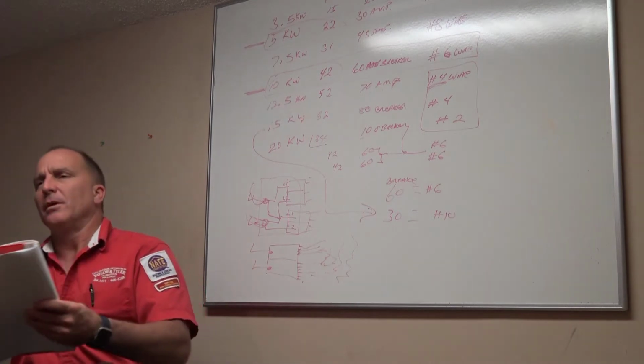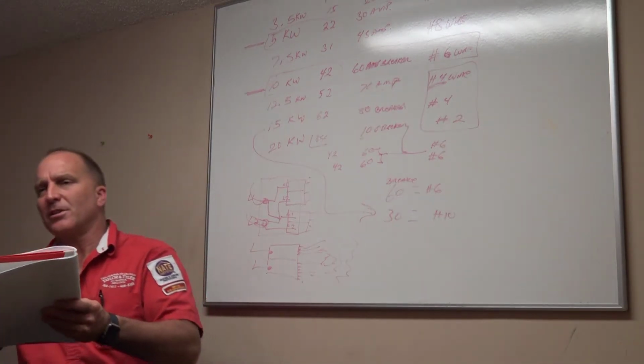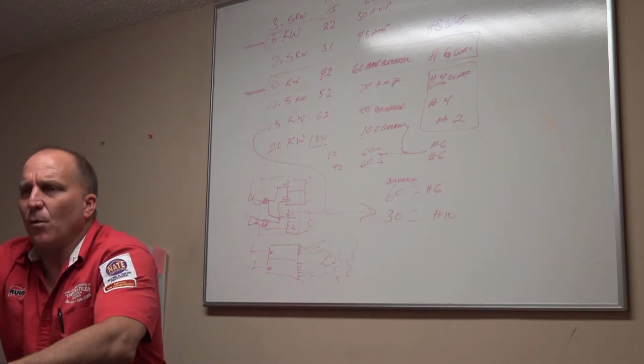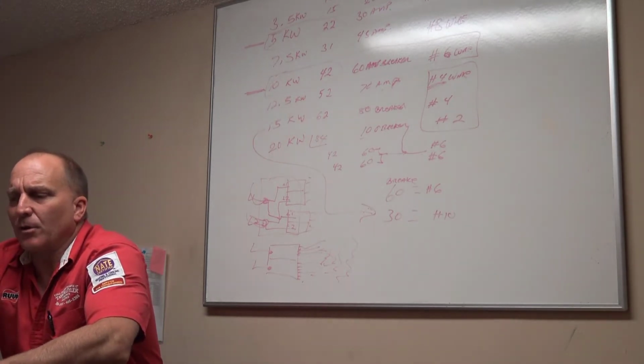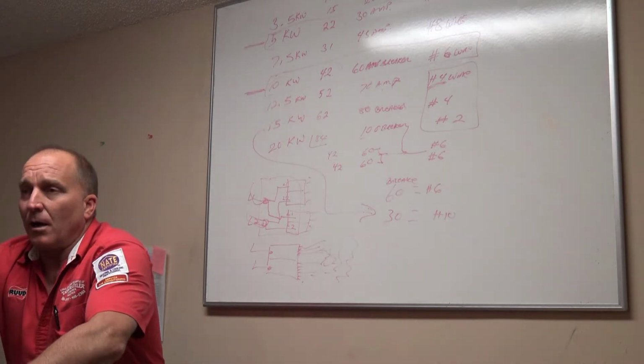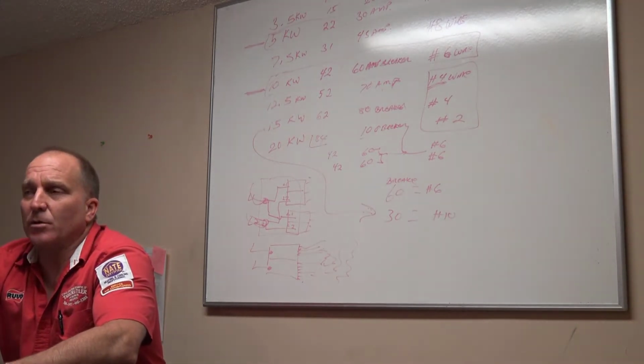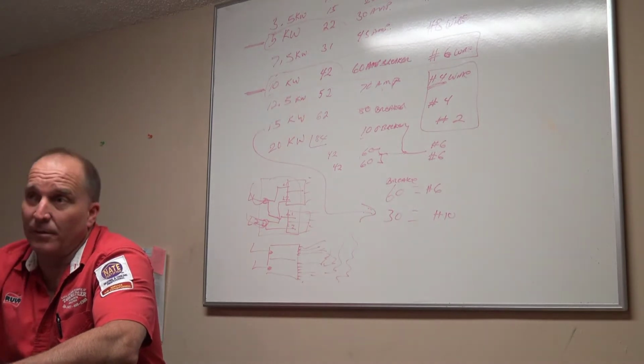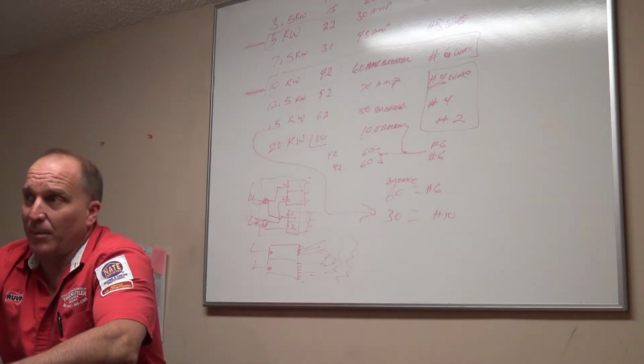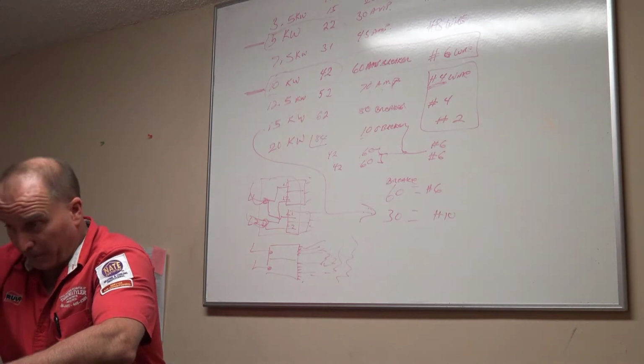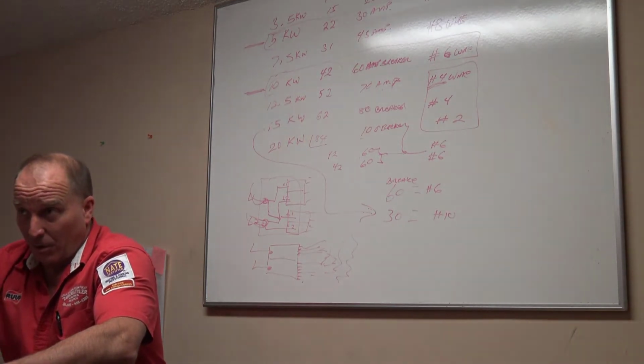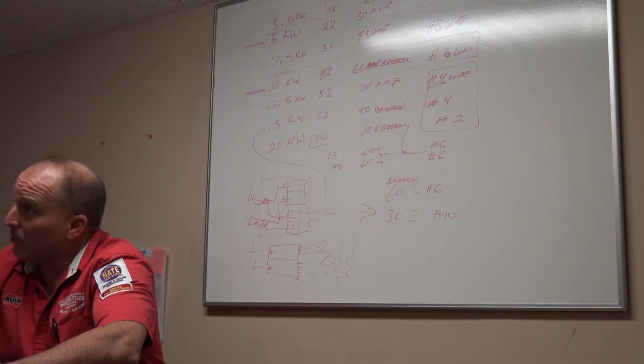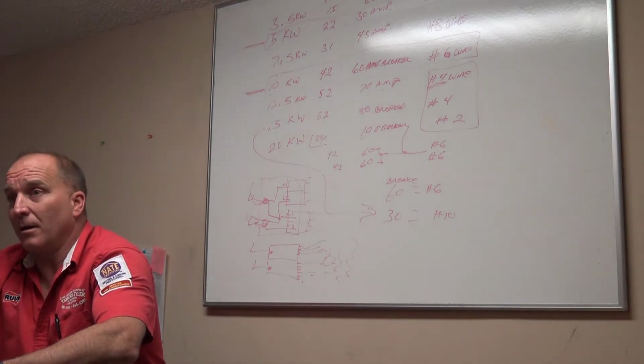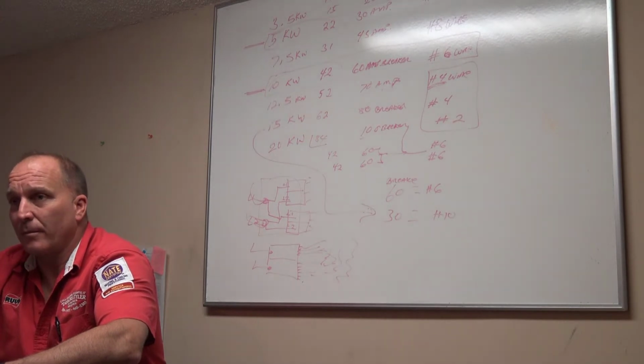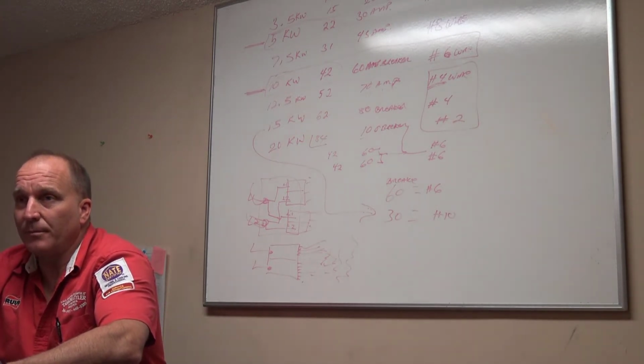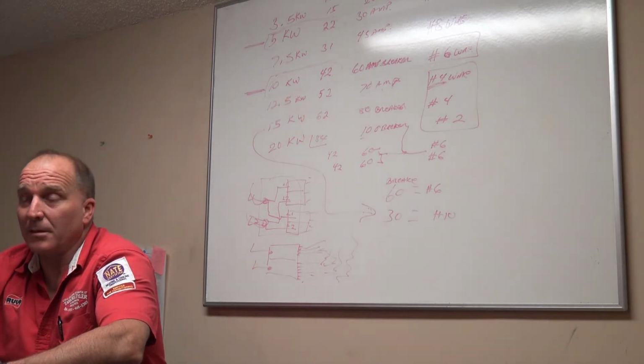So I just told you, if that limit switch is opening, you need to check your static pressure, right? What are you checking for in static pressure? Low static pressure, low airflow, dirty filters, dirty evaporator coils, blower wheels dirty, restricted return, supply air is not opened up enough, supply plenum is blocked off, collars are shut, dampers are shut, grills are shut. Just a list of things that reduce airflow. Blower motor set on the wrong speed. Okay? That's a list of things.